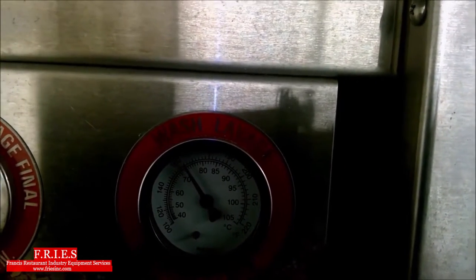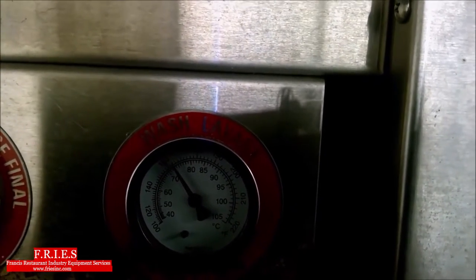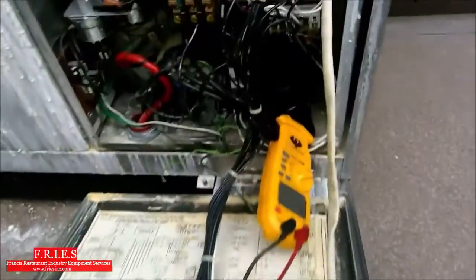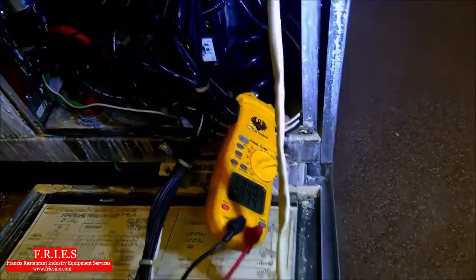So the wash now is at about 162. So what I'm going to do now is do a dry fire test. I'm going to empty water from the unit and make sure that the pressure or the float switch is not giving issues. Alright, so I'm not drawing any amperage. We're not dry firing.